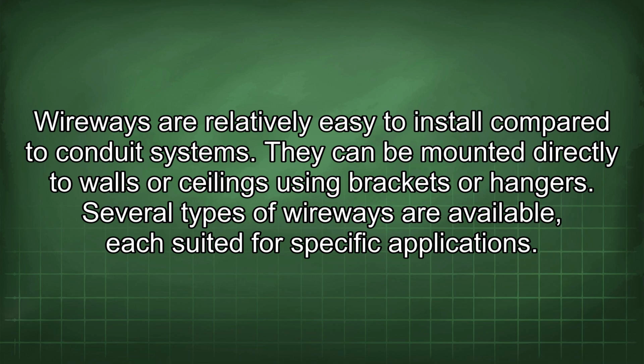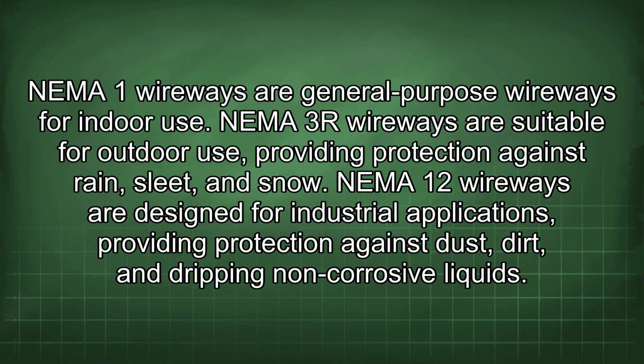Several types of wireways are available, each suited for specific applications. NEMA 1 wireways are general-purpose wireways for indoor use. NEMA 3R wireways are suitable for outdoor use, providing protection against rain, sleet, and snow. NEMA 12 wireways are designed for industrial applications, providing protection against dust, dirt, and dripping non-corrosive liquids.